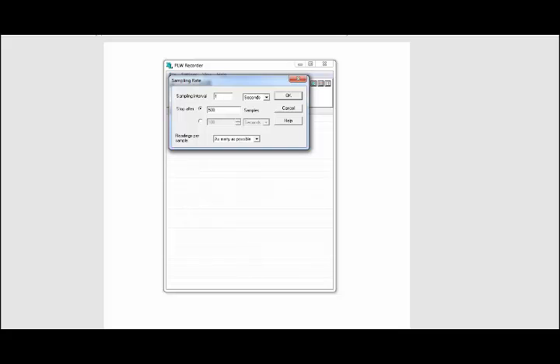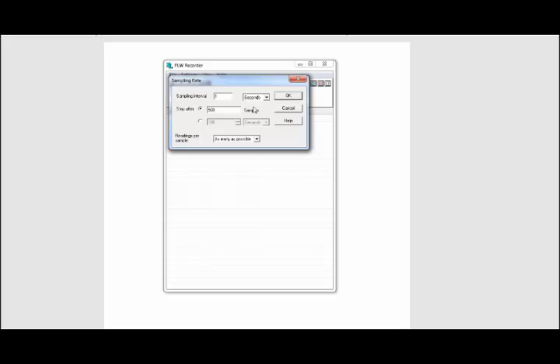Sampling Interval is how fast you want it to record for each channel. With the TC-08s you can record up to 100 milliseconds per channel. Here we're just going to keep it at one second. You can tell it to stop after so many samples or stop after a certain time period. I'm just going to leave it at the default 500 samples and click OK.